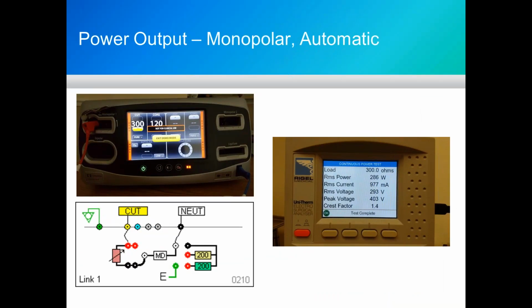So we'll be doing our first test on Monopolar 1. The good news here is the number of power tests that one must do has been greatly reduced. We were fortunate enough to have a working relationship during development of this process. It's one of the topics that was a discussion point. As you remember with the triad, the FX, you do every power test on every energy port. So with Monopolar, you do it on Monopolar 1, you would do it on Monopolar 2, you would do it on the UFB port as well.